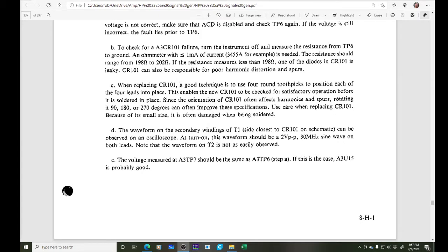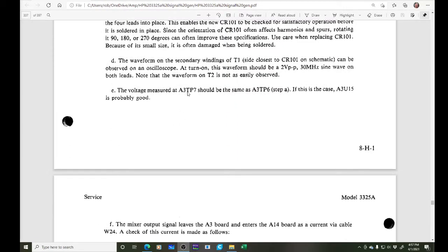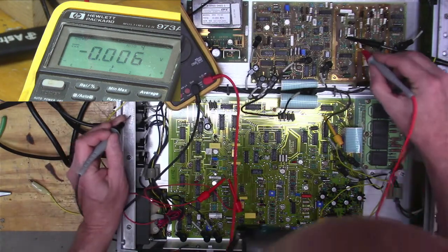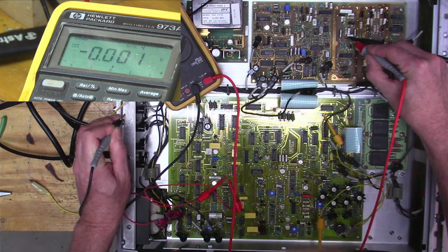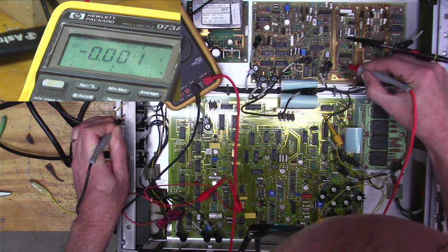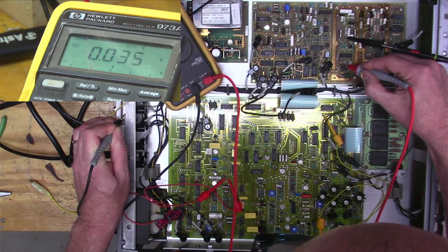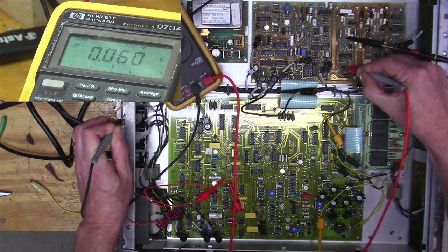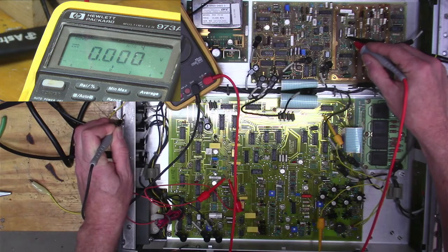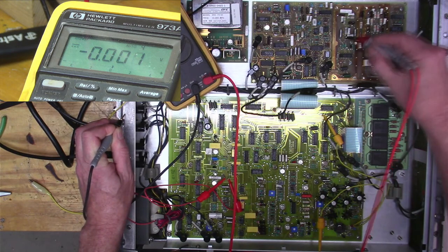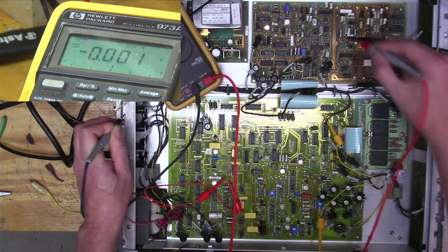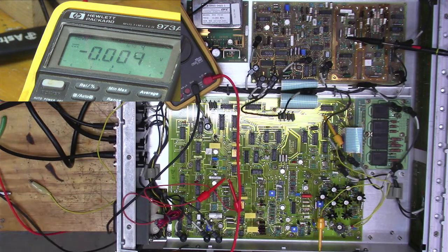And then it says the voltage measured at A3 TP7 should be the same as A3 TP6, right? And if this is the case, then A3 U15 is probably good. Well, let's check those. All right, so here's 6. Right at 0. And 7. It's close. We're about 60 millivolts off. Right? But the thing is that, so that doesn't give us much of an indication.